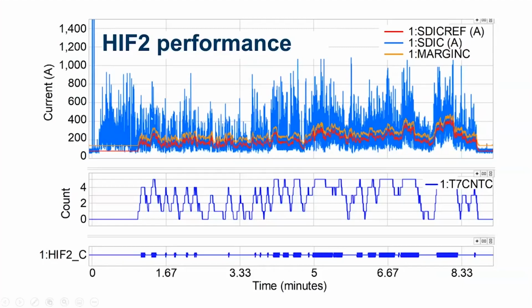Based on how much the SDI quantity deviates from the margin, the orange line, over a certain period of time, the relay integrates or adds these counters. There is a counter named T7CNTC. There is a T7 counter and a T8 counter. For the tripping bit, we use the T7 counter. If the deviation from the margin is very high, you're going to see this counter increasing. But when the deviation starts getting lower, the integrating counter also starts getting a little lower.